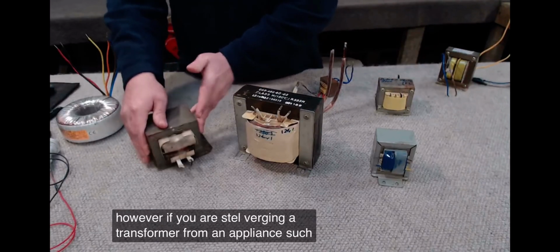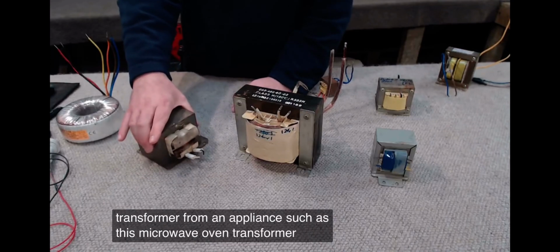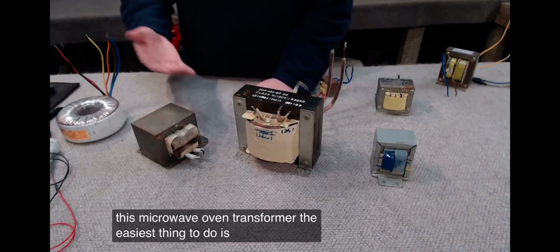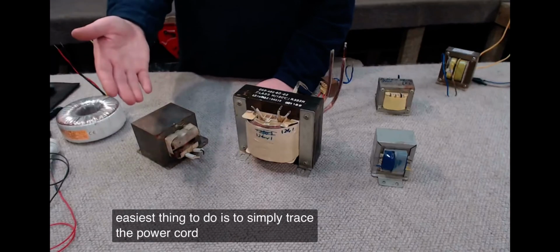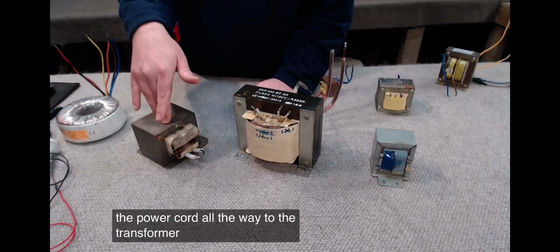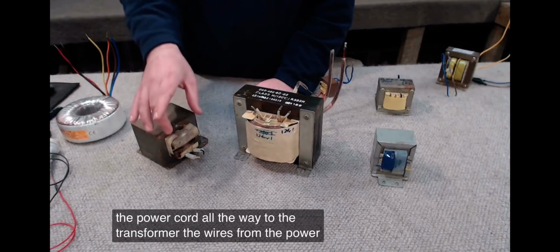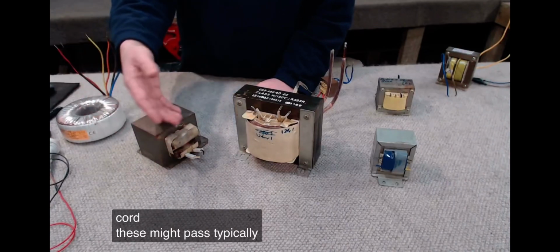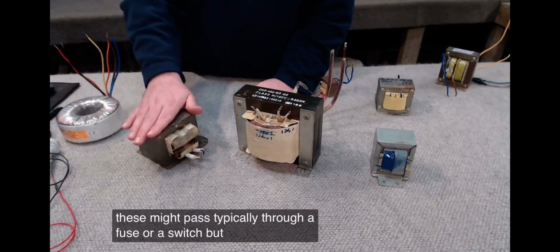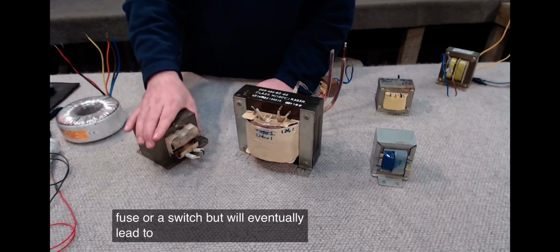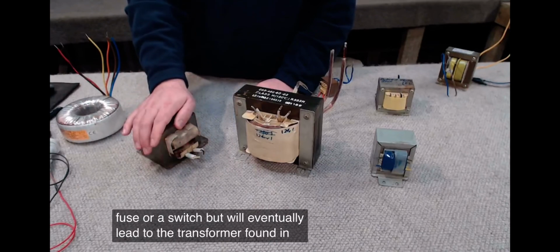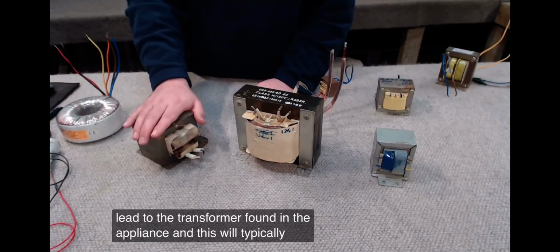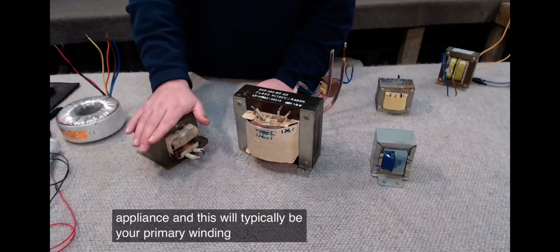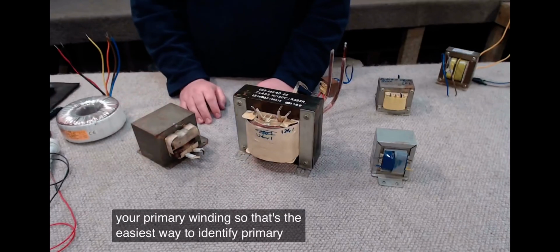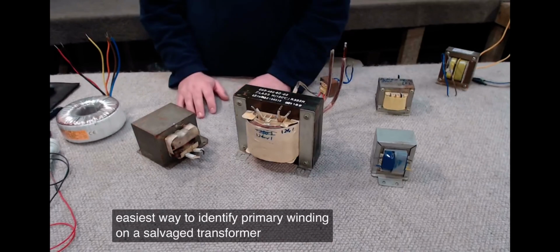However, if you are salvaging a transformer from an appliance such as this microwave oven transformer, the easiest thing to do is to simply trace the power cord all the way to the transformer. The wires from the power cord might pass through a fuse or a switch, but will eventually lead to the transformer found in the appliance, and this will typically be your primary winding. That's the easiest way to identify the primary winding on a salvaged transformer.